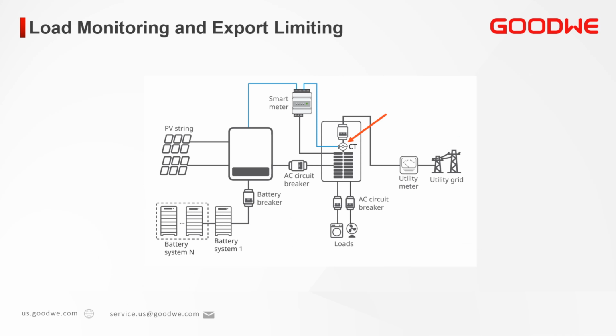The GM K120 meter is included on these models, and it can be helpful by providing additional information to the system owner, such as load monitoring. The GM K120 is revenue grade. You can locate a certification to ANSI standard on our website. The CTs should be installed on the main service panel before all of the loads. Please note the position highlighted by the red arrow. Note that if the CTs do not reach the main panel, there are a couple of ways to extend them.